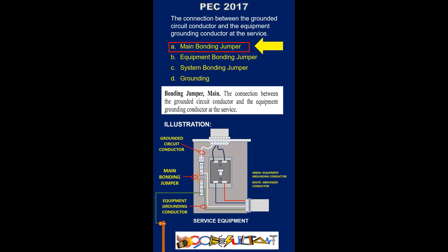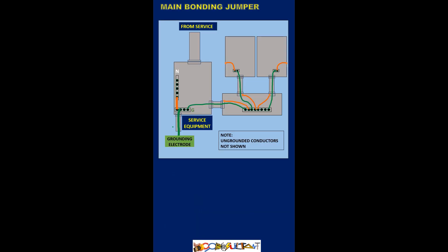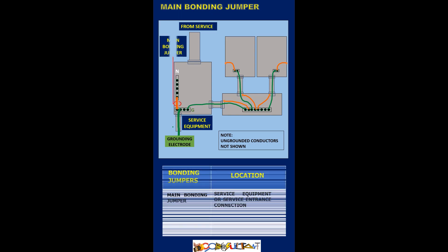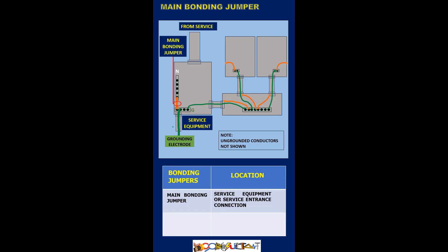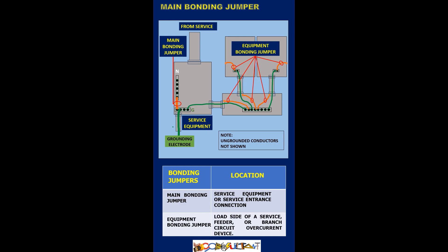Sometimes the grounded conductor is linked to the grounding electrode conductor. It's important to differentiate between an equipment bonding jumper and a main bonding jumper. The main bonding jumper is located in the service equipment, while equipment bonding jumpers are installed on the load side of a service feeder or branch circuit overcurrent device.